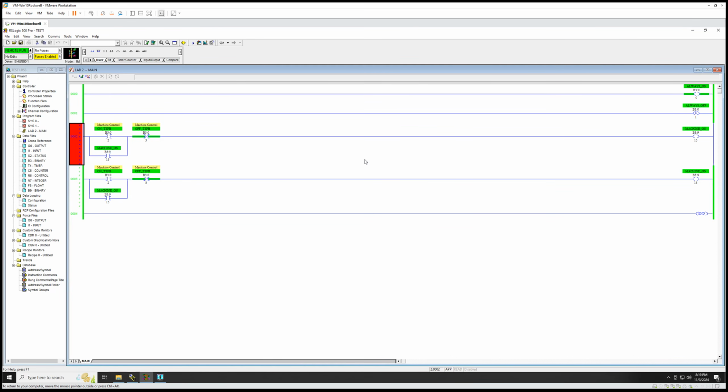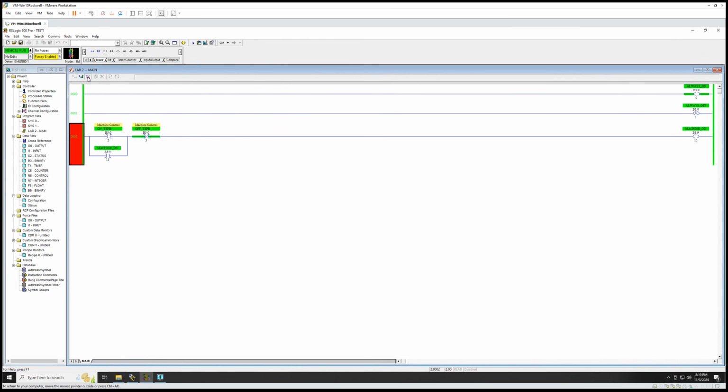so you only want to do it if you know that it's safe to do on the machine, as your program would not match with the PLC if you get hung up like we just did here, and you would have to upload, and once you upload, all your comments go away on an SLC. So just keep that in mind if you're trying to do online edits with this processor. Let me cancel out of this, and that's what we have as far as the on and off.